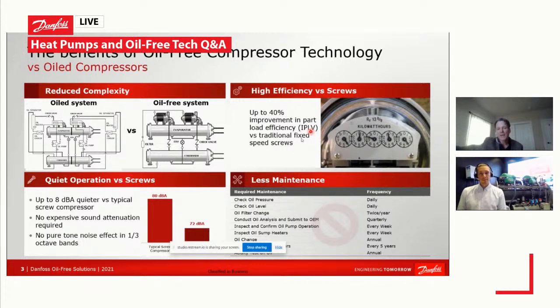And it also, and this is kind of a byproduct of those technology choices, but if you go oil-free and you do it based on going with centrifugal compression on the front end, and then permanent magnets as well as trim magnets or magnetic bearing based design, then you have no contact in the compression, either the front end or the back end. The byproduct of that is that it's extremely quiet. And so you'll hear this or not hear this based on where Jonas is standing right now with those units operating. And of course you can't hear them. And so that's a very good illustration of that lack of sound that's coming out of those units.